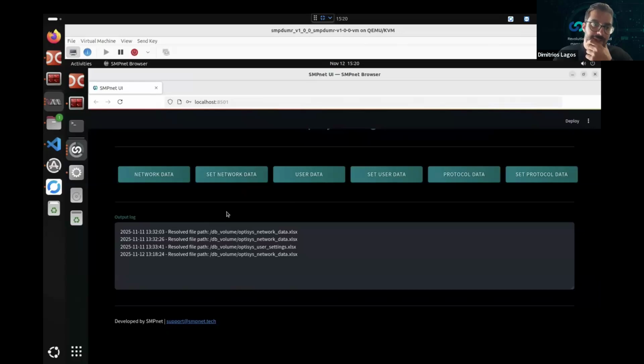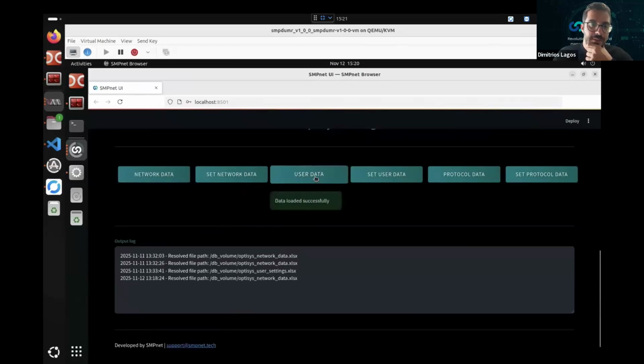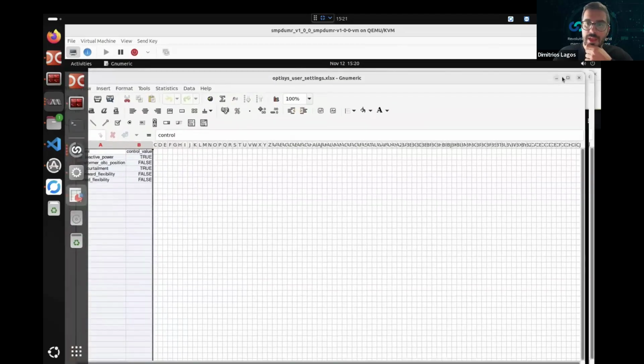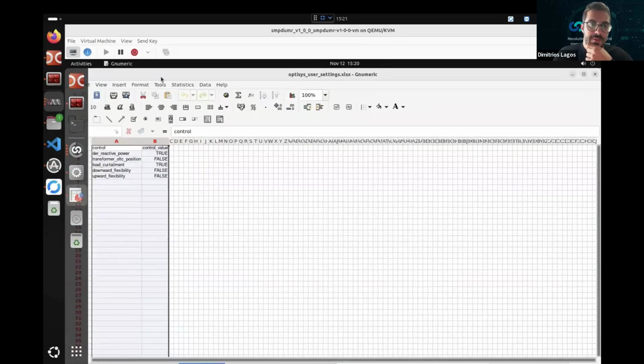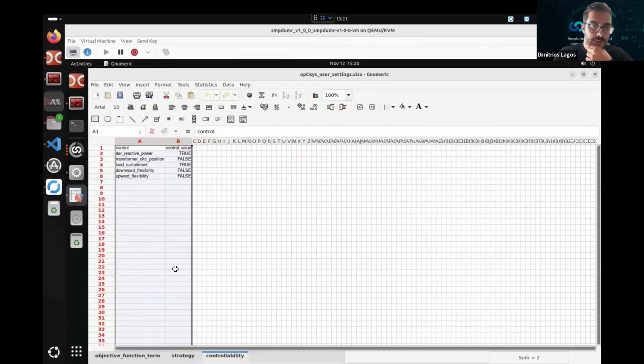Of course, this is only for the static data. Optisys constantly updates the network based on the latest status of the switches. So if a switch disables a line, this is also taken into account in the digital twin model and being considered by Optisys. So apart from network data, we have the user data. In that file, the user can set the different options in control. So for example, by setting control value of DER reactive power to false, only active power can be used for voltage control. Whether Optisys can control the OLTC tap change, this is also something that can be introduced in this sheet.